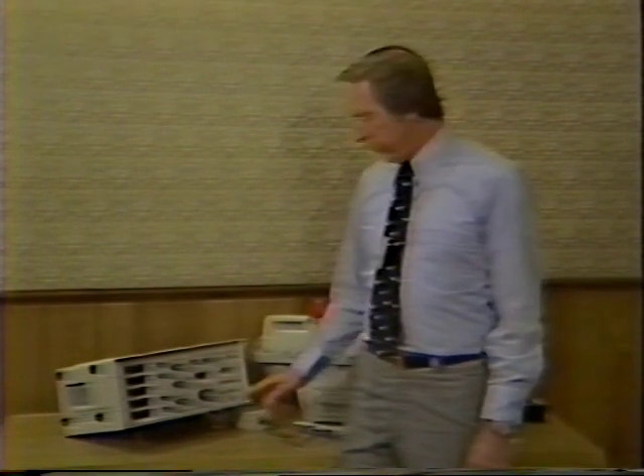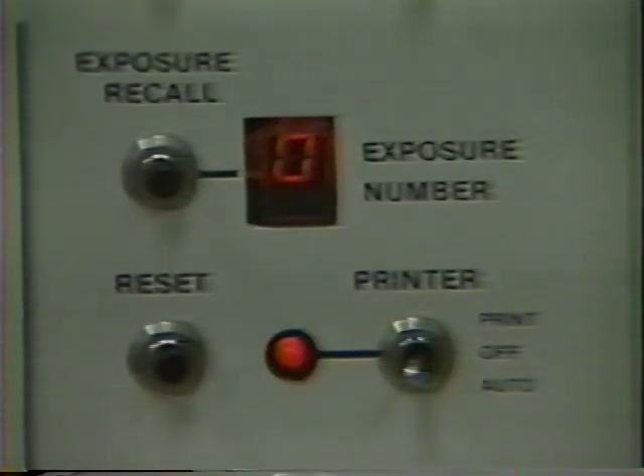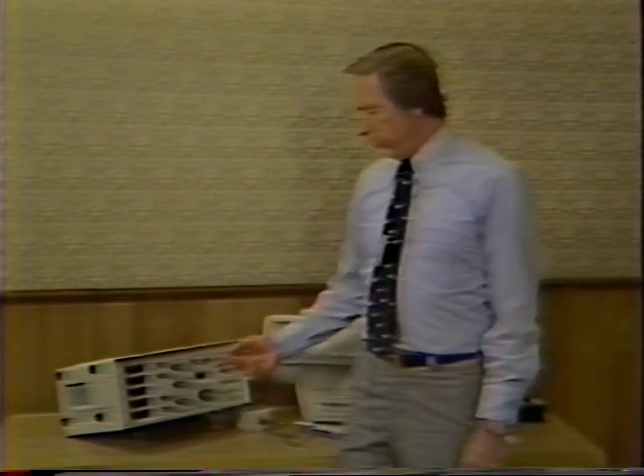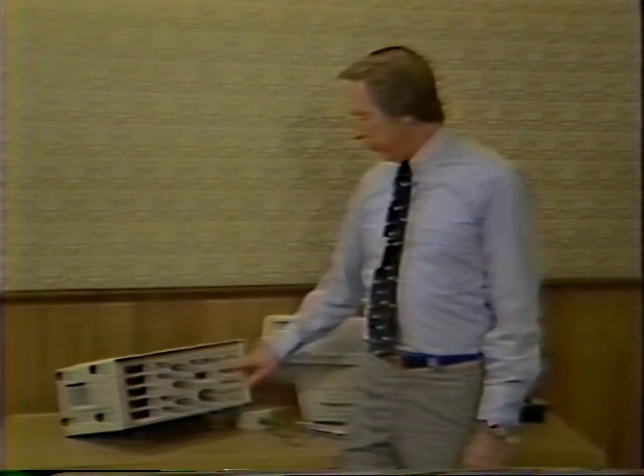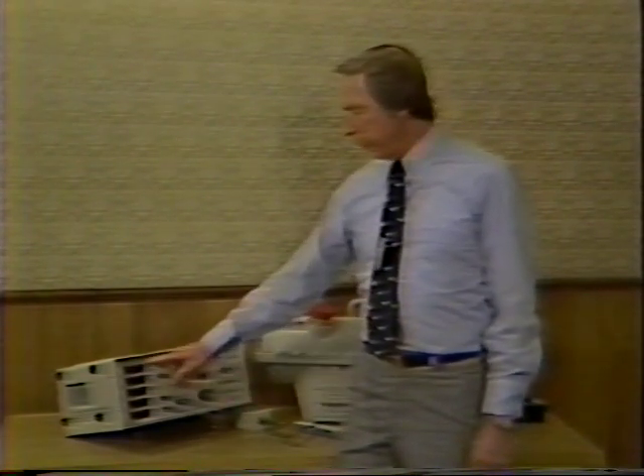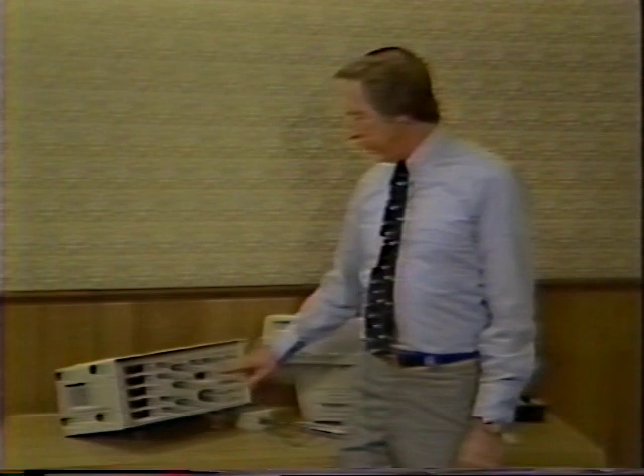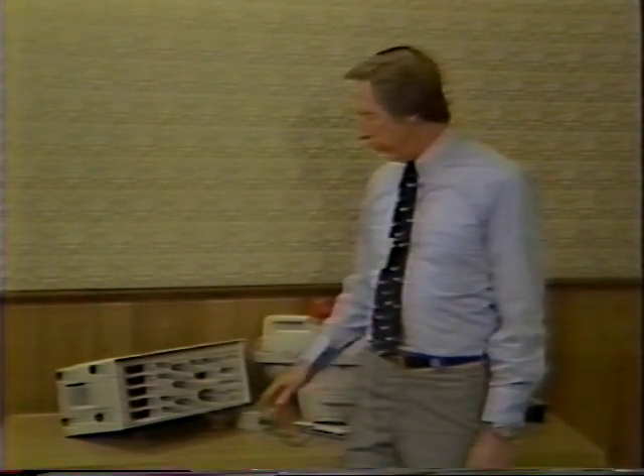We have another feature in the Dynalyzer that we consider quite excellent. We're able to recall any of the 10 exposures that we have in memory back to have a look at them for further analysis. We depress the button. We would bring back exposure number 9, press it again, exposure number 8, and so on, down through 1, and then back to 10 again, and we can continue around the loop. Excellent feature to be used for troubleshooting.